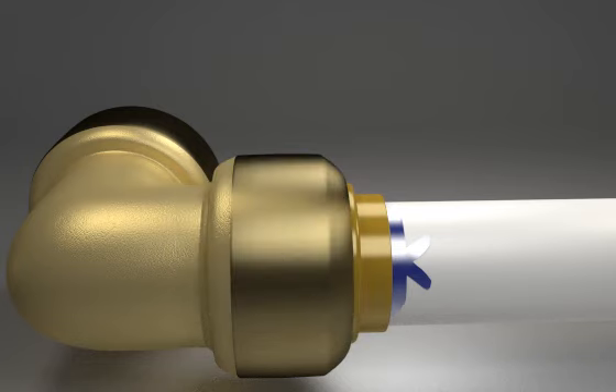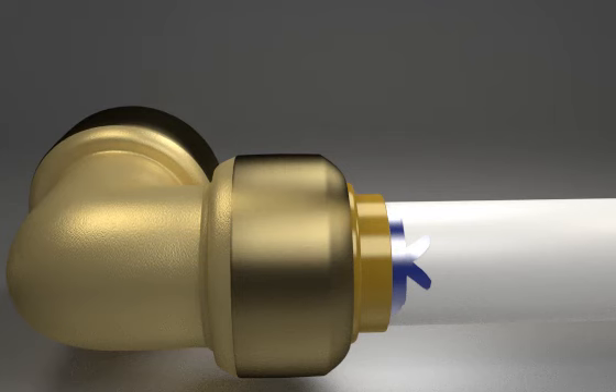To ensure the joint is secure, pull the tube and fitting in opposing directions. The tube will continue to revolve within the fitting as a feature of the Tectite range. The joint is now ready to deal with pressures up to 6 bar, at temperatures of up to 95 degrees C.